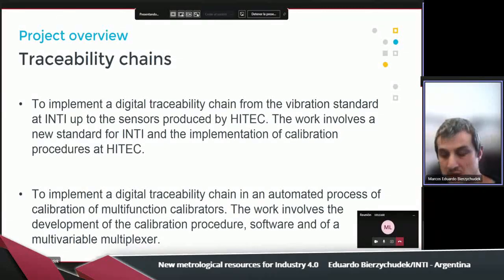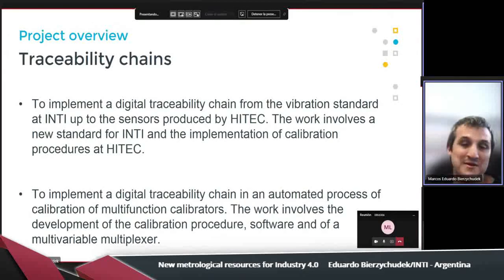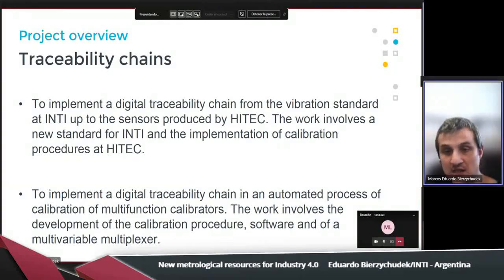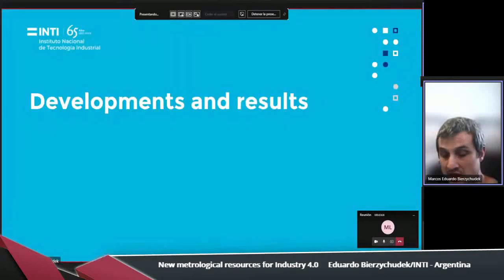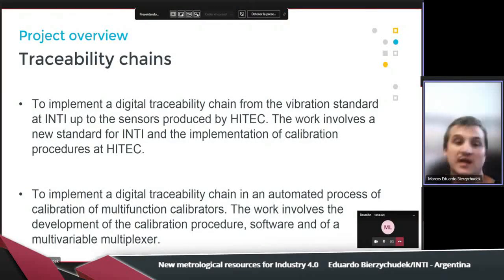In this case, this example is quite important, because the calibrator needs more than 100 calibration points. So the certificate used to be very large. And in this way, we are giving an example of another powerful application of the DCC, where you have very large calibration certificates. We are also interested in the automatic multifunction calibrator, because nowadays this process is semi-automatic here at INTI, and we believe that this can also be applied in private laboratories. And nowadays in Argentina, we have just one laboratory that can perform this task. So we're interested in creating more offer of this service.